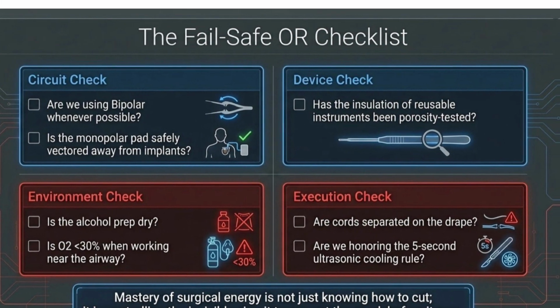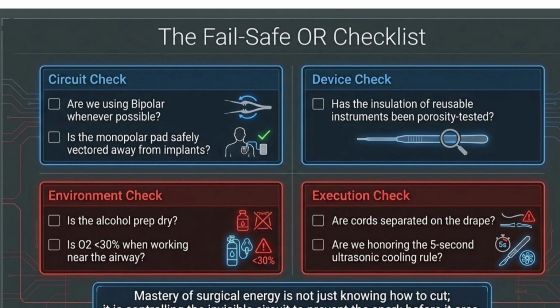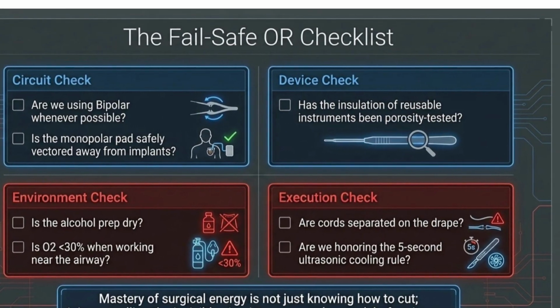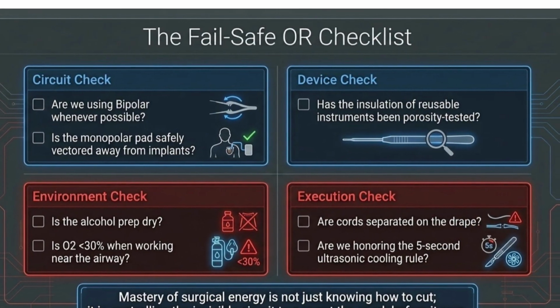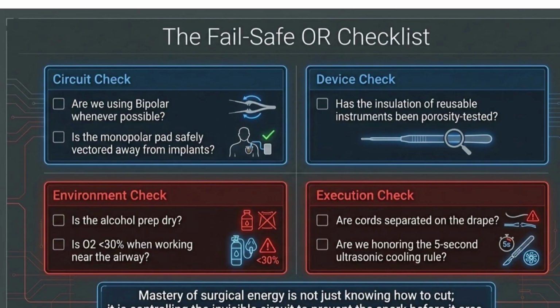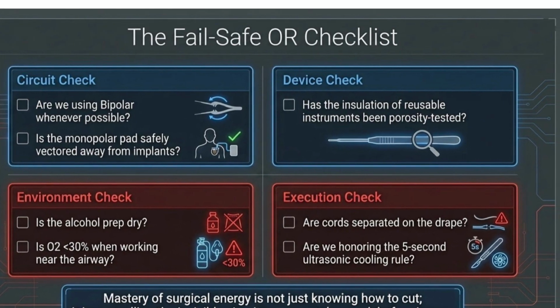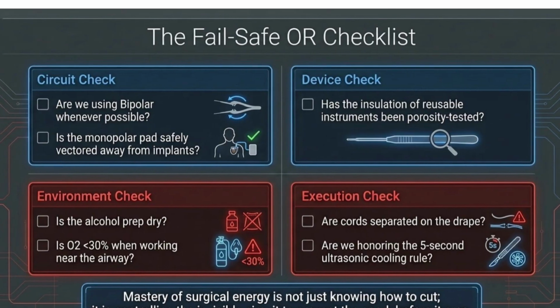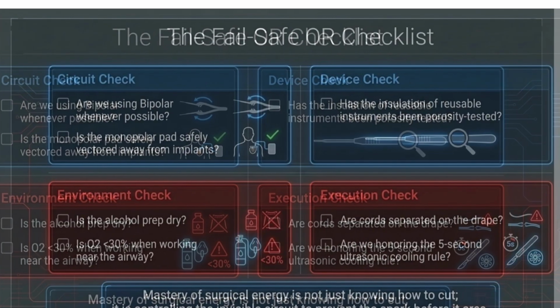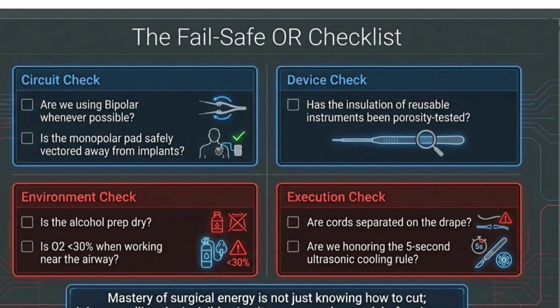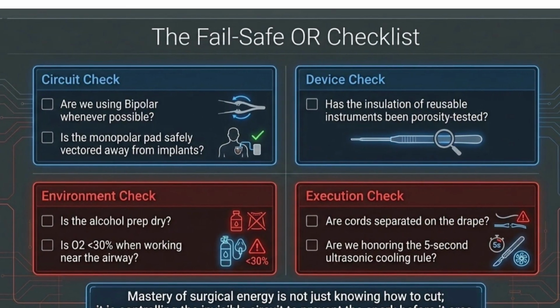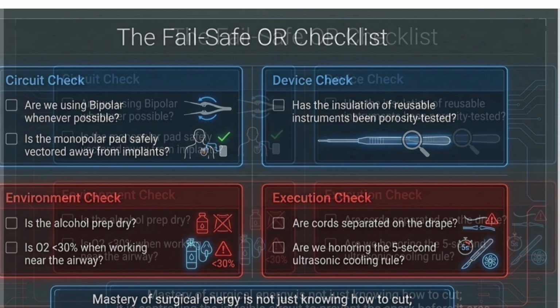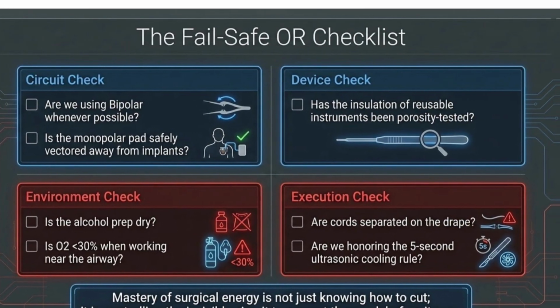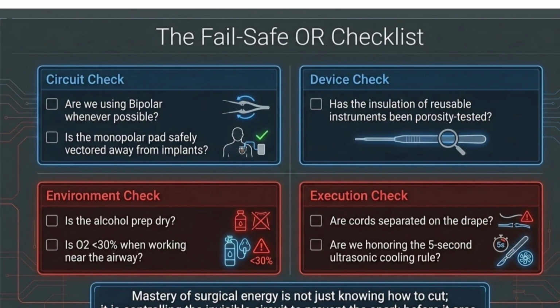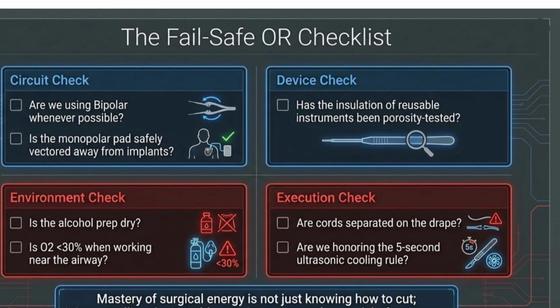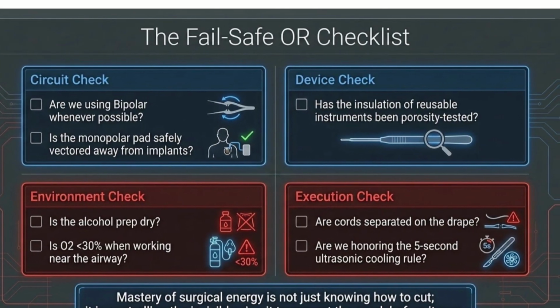The checklist for safety. So, the circuit check: are we using bipolar whenever possible? Is the monopolar pad safely vectored away from implants? In device check: has the insulation of reusable instruments been porosity tested? In environment check: is the alcohol preparation dry? Is oxygen less than 30% when working near the airway? Execution check: are cords separated on the drape? Are we honoring the 5-second ultrasonic cooling rule? Mastery of surgical energy is not just knowing how to cut, it is controlling the invisible circuit to prevent the spark before it arcs.